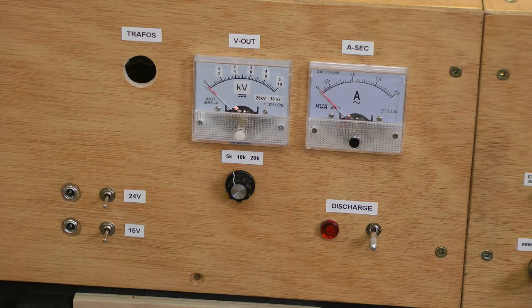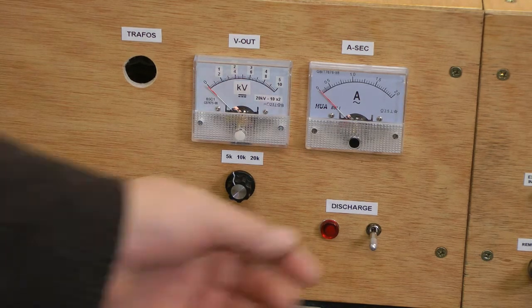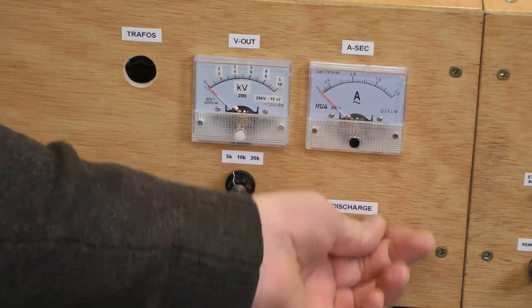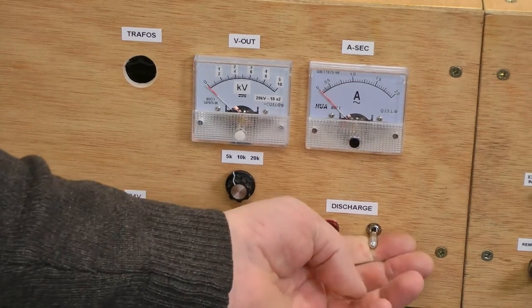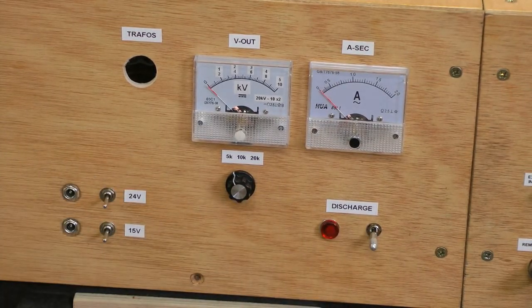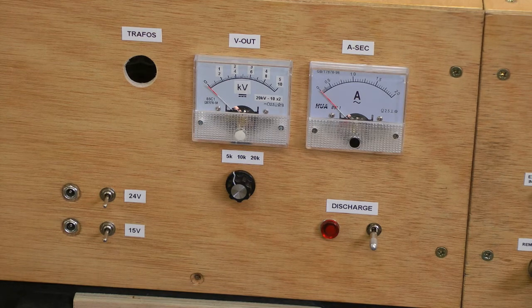There are 2 series vacuum relays on the input and 2 series vacuum relays on the output of those, so on the positive and negative sides. So nominally 12 kilovolts through the resistor chain, and that allows for safe discharging of a large capacitor bank. That can be switched here. Again, this is a lock switch, so it doesn't accidentally get put on. That can also be controlled from the remote control as well.